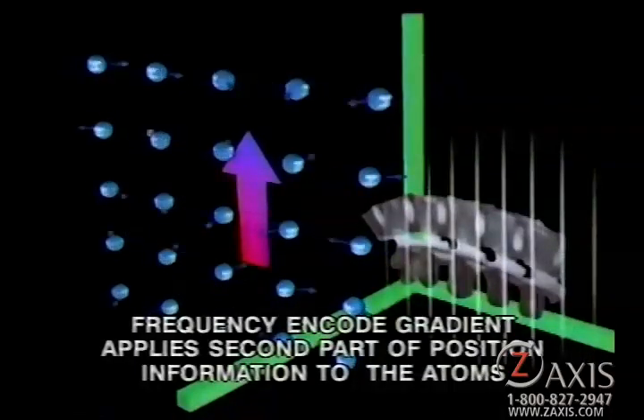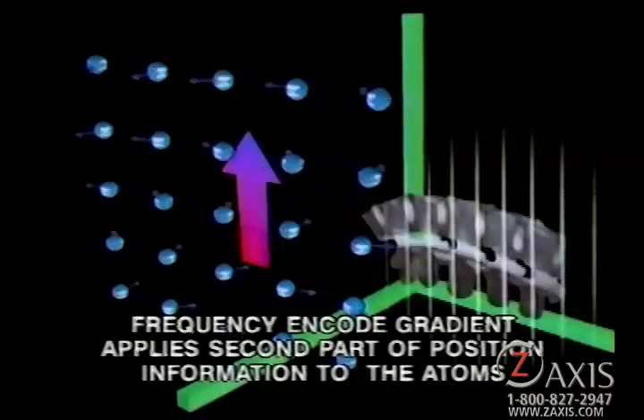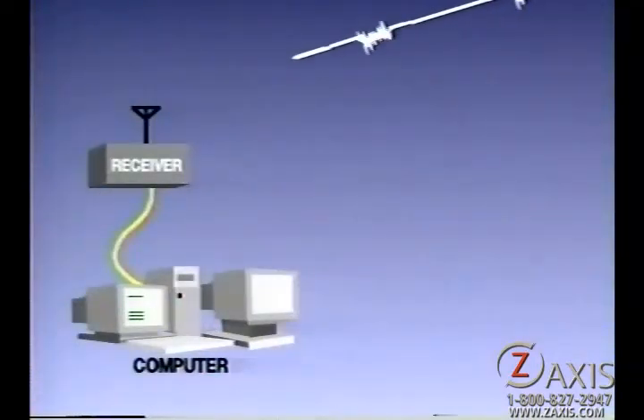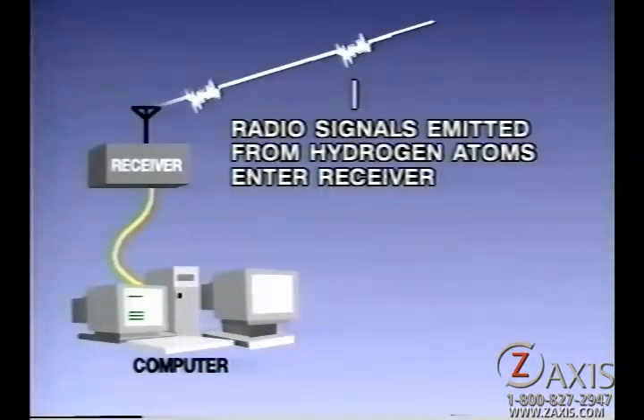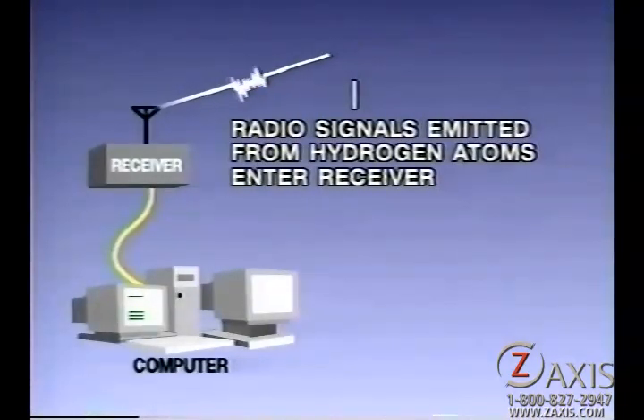Next, another magnetic gradient at right angles to the first forces the protons to spin at different frequencies depending upon the strength of this field. These different frequencies will be used to determine the proton's position along the y-axis of the patient. The other part of the story is that these spinning protons emit radio waves. These radio waves carry information about the position of the proton as well as the condition of the tissue in the T1 and T2 times. These radio waves are picked up by an antenna that is wrapped around the patient. A radio receiver amplifies these waves and sends them to a computer where they are converted into digital data and analyzed.